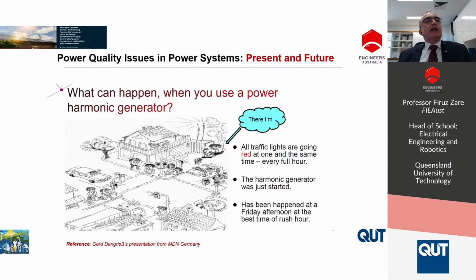This is one example that one of my colleagues from a distribution network in Germany reported: the traffic light was disturbed because of high frequency harmonics generated by one of the devices, and they realized that the control system was affected and the traffic light didn't work for hours. And that's one of the reasons that they realized that the resonance frequency of the control system was tuned at the harmonic frequency of the other device.